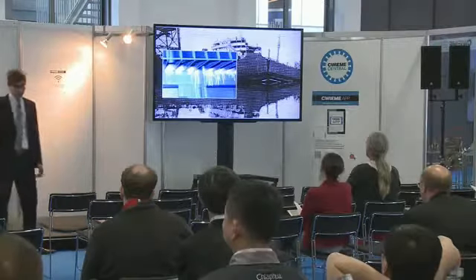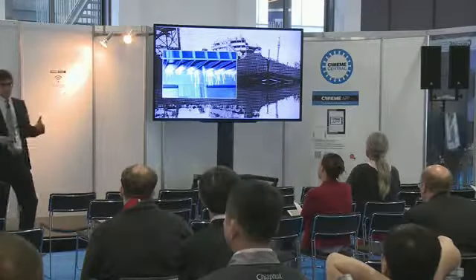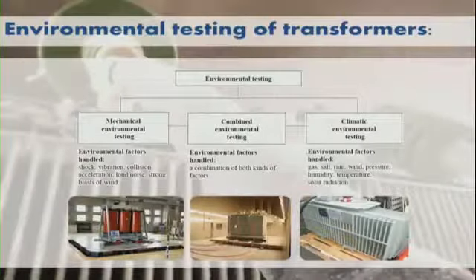And there have been some problems in the field as well with transformers. There has been leakage, whether it's related to vibrations or climatics, we don't know yet, but that's why we are doing the research. On the right-hand side is a crack because of extreme cold on a resin cast transformer, because the material becomes very brittle, and then if you have a thermal shock, you can have these problems. How can we mitigate it?